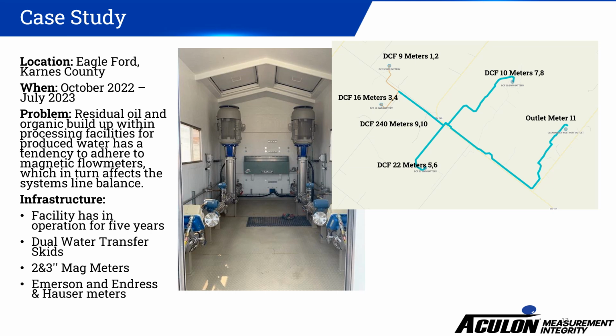The problems we were facing were residual oil and organic buildup within the process facilities for produced water, as these have a tendency to adhere to magnetic flow meters, which in turn affects system line balance and leak detection. The infrastructure of this test was a closed-loop system consisting of 5 dual water transfer skids and 1 outlet meter. Each of these dual water transfer skids and system have been in service for just over 5 years. The water transfer skids consist of 2-inch mag meters, and the outlet meter is a 3-inch mag meter. We have a mixture of both Emerson and Endress+Hauser meters.